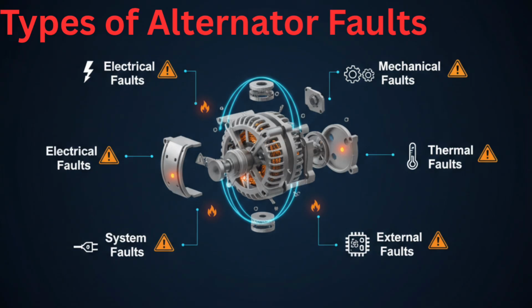Mechanical faults involve bearing wear, rotor imbalance, shaft misalignment, or coupling damage. Thermal faults arise due to excessive heating in stator windings or bearings, often caused by overload or cooling failure. System faults occur due to synchronization errors, unequal load sharing, or PMS malfunction. External faults include busbar short circuits or downstream equipment failures that indirectly stress the generator. Understanding fault classification helps engineers quickly diagnose the root cause during emergencies. In marine practice, correct identification of the fault category determines which relay or protection device will operate.